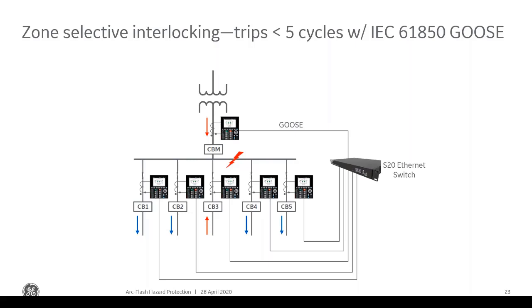And so it kind of defeats the purpose a bit. If I have to add some sort of timing delay, then I'm increasing the arc flash energy. And two, if I need to increase the sensitivity, then I might not be capturing all arc flash incident events. So a better technique is zone selective interlocking. It's very fast. It could trip in less than 5 cycles, depending on the design.